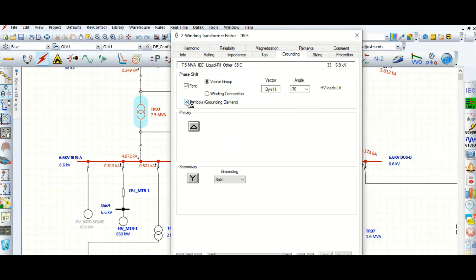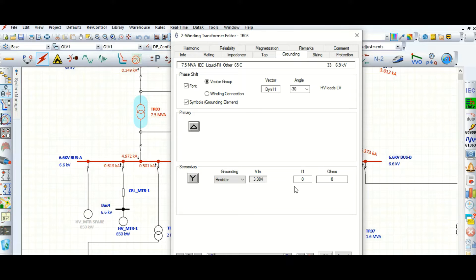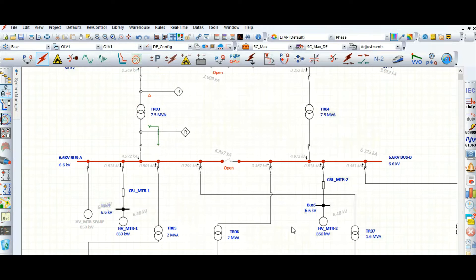Checking the grounding symbol box will show the delta-star connection — primary side delta, secondary side star with secondary side grounding. For this 6.6 kV system, I want to provide a resistance grounded system and limit the grounding current to 300 amperes. You can drag and position the symbol — this is delta, this is star, and this is the resistance grounding system.